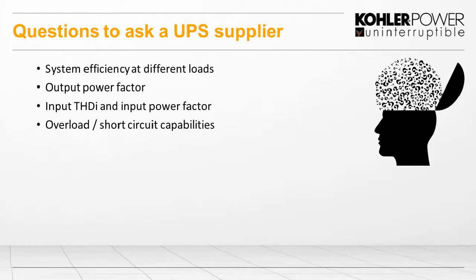And how is it rated on the output power factor? Is it unity output, which gives you more power and is equal to the kVA, or is it at 0.8, for example? The input THDI and input power factor can make a big difference on your input supply, so we should be making sure that that is good and suits your needs. And again, the overload and short circuit capabilities of the output, the inverter: how good is it, and does it do what you require in the event of those situations?